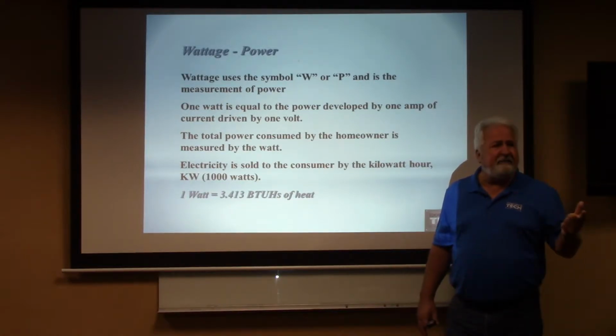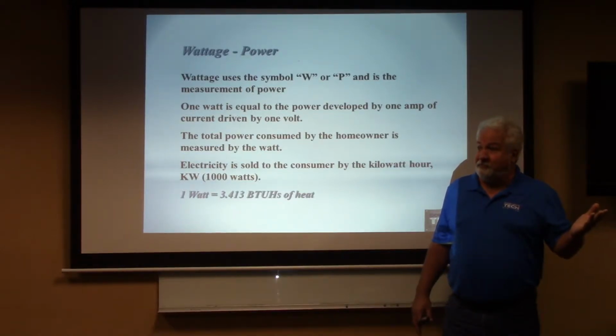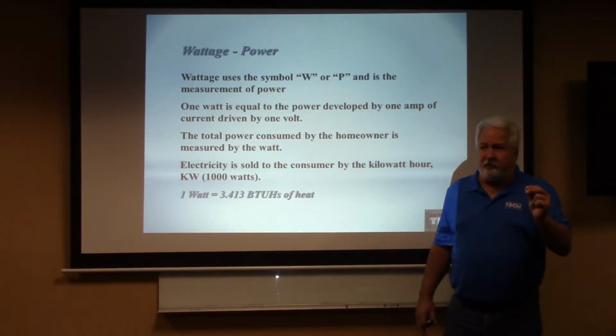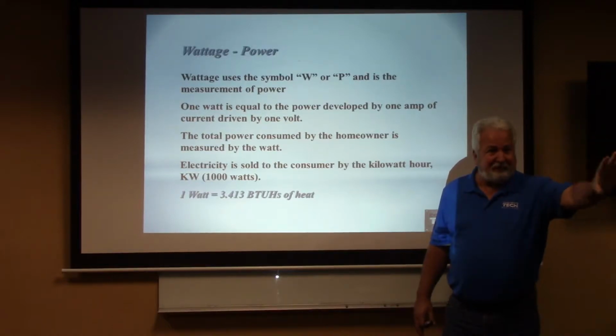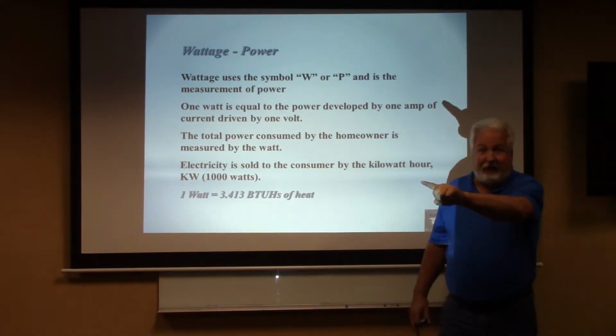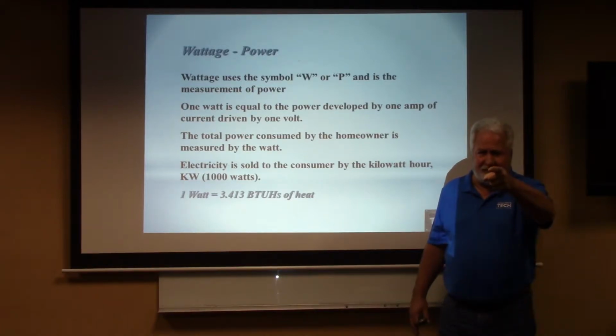When a heat pump goes into defrost, how much cooling is taking place in that house if it's a 3-ton? 3 tons, so that's 36,000 BTUs. So when it goes into defrost, it's producing 36,000 BTUs of cooling in that house. Everybody with me so far? We bring the heat strips on for what reason? To combat the cooling. Okay, so we said it's 10 kW.